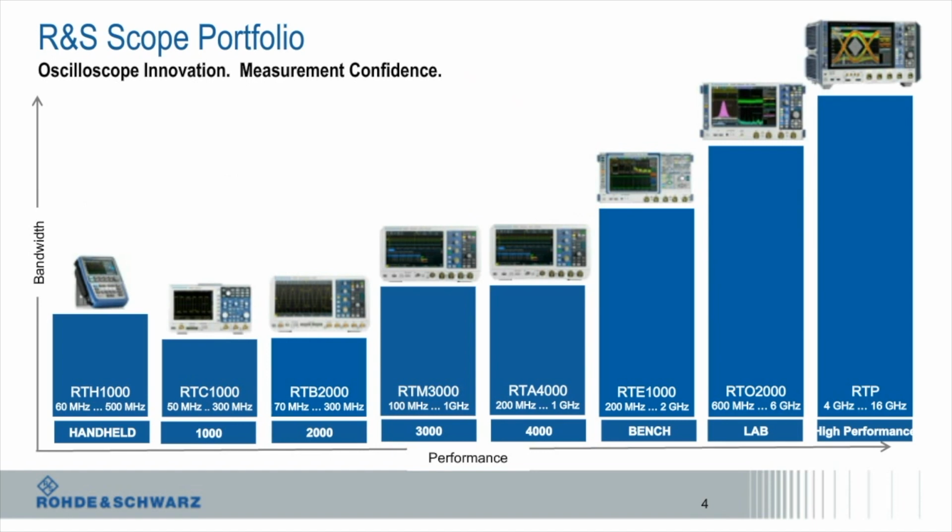Today, I'll be showing measurements from a Rohde Schwarz RTO oscilloscope. If you are using a scope from another vendor, the same techniques are still applicable. Oscilloscope manufacturers will have certain scopes in their portfolio that are better suited for power integrity measurements. For Rohde Schwarz, it's the same. These scopes typically have lower noise, better FFT capabilities, and other characteristics that allow them to make better power integrity measurements.